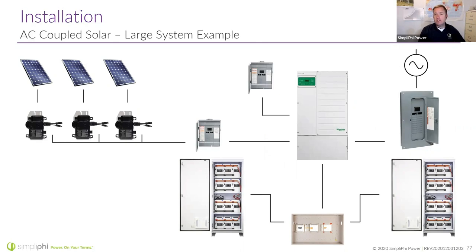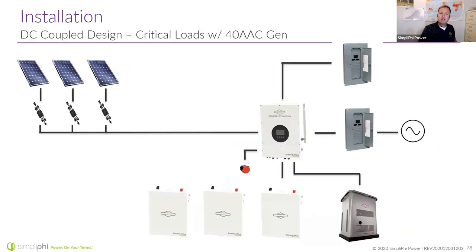Here's what an AC coupled system can look like. I want to drive home the fact that our batteries are inverter agnostic and charge controller agnostic. Come out to someone's house with IQ7 Plus micro-inverters — we're back-feeding AC into a Schneider, we have our critical load subpanel, grid with non-backed-up loads, and two Boss 12 cabinets. If you just have one Boss cabinet, you wouldn't even need the combiner — just feed directly up from that Boss 12 to the Schneider. Our inverter also supports DC coupling with a built-in AP Smart Systems transmitter for rapid shutdown.